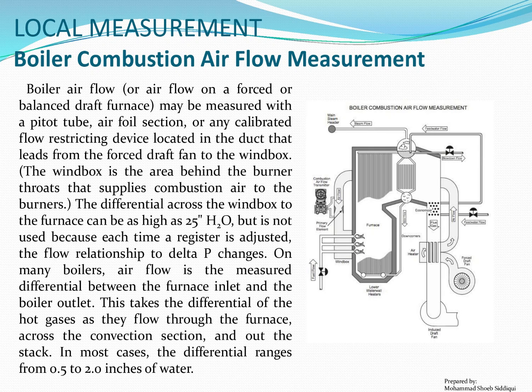On many boilers, airflow is the measured differential between the furnace inlet and the boiler outlet. This takes the differential of the hot gases as they flow through the furnace, across the convection section, and out the stack. In most cases, the differential ranges from 0.5 to 2.0 inches of water.